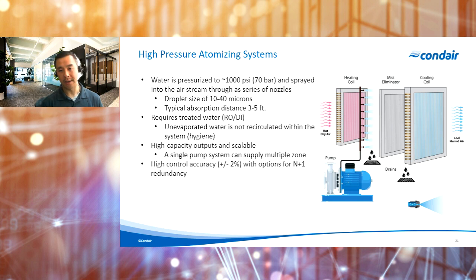Now, if we compare that to an evaporative media system, these will typically consume a bit more energy. Again, because we do need treated water, so that's either reverse osmosis or deionized water, there's going to be energy associated with the water treatment side. And then we do also have a high pressure pump motor in there as well, but still significantly less than a traditional humidification or DX cooling system. So to give you an idea here, a system capable of outputting about 1,700 pounds an hour will consume about 3 kilowatts of electricity.